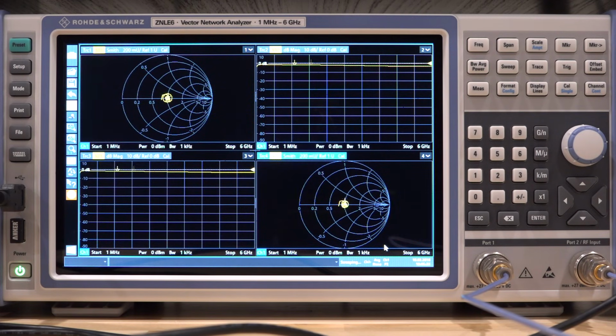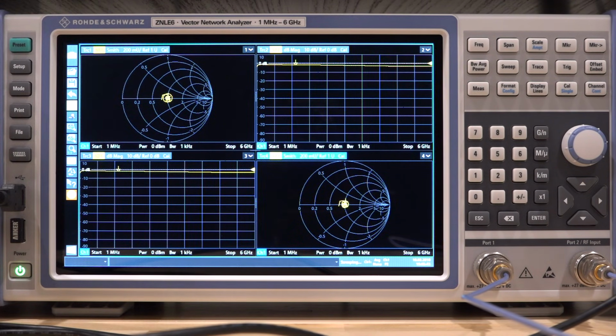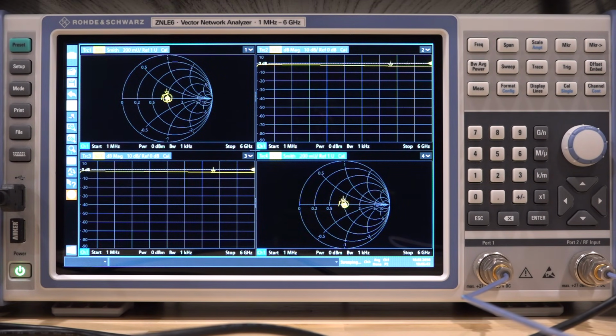And there it is. We are now calibrated. Now the impedance of the cal unit is not known, so you can't rely on this measurement to judge whether your calibration was good or not. That's just because there is a droop here doesn't mean that the calibration wasn't good. So now we are fully calibrated. We can actually go ahead and start doing some measurement. So let's do something very basic just to make sure our calibration even makes sense. Let's connect a 50 ohm termination onto it just to see what happens, and then we will measure our filter.